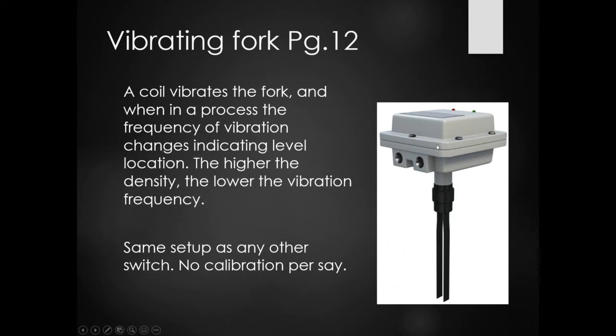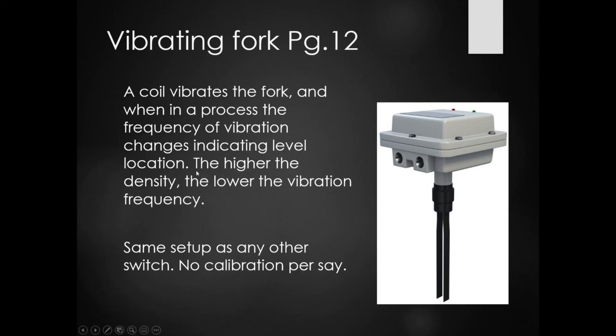Last but not least, the vibrating fork operates on a very similar principle to the vibrating diaphragm. A coil vibrates the fork — like a tuning fork, when you touch it the pitch changes. When in a process, the frequency of vibration changes, usually getting lower, indicating the level location. The higher the density of the material, the lower the vibration frequency. It detects the change between the higher frequency when not in the process and the lower frequency when it is. Same setup as any other switch — no calibration per se.